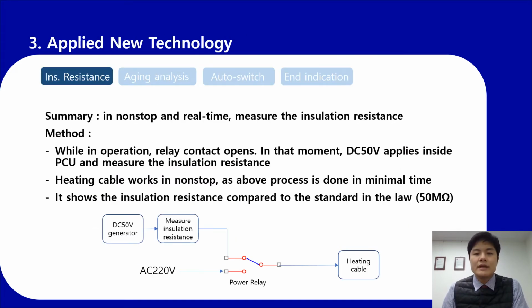Existing technology cannot measure the insulation resistance while electrical current is applied, but we automatically measure the insulation resistance in the minimal time when the relay contact is open. Thus, non-stop operation becomes possible. Currently, many customers are interested in this technology. We completed the application of the patent in Korea, and we are also planning to apply for the patent in other countries.